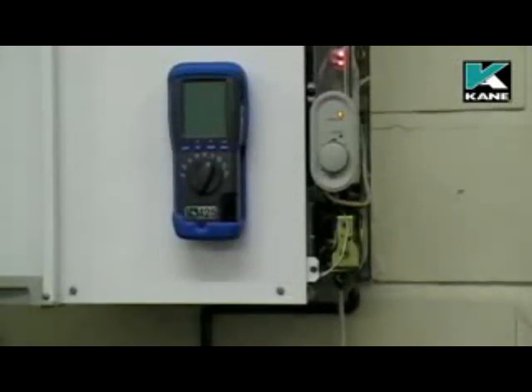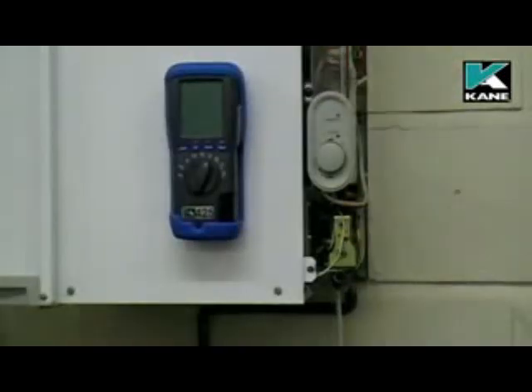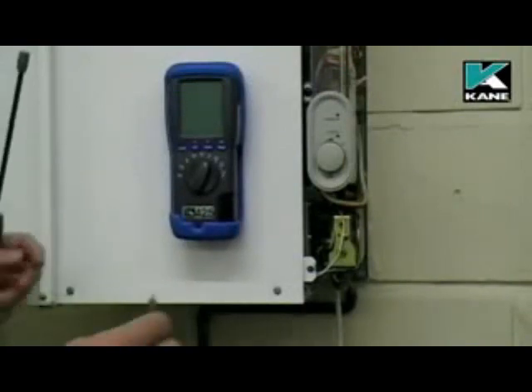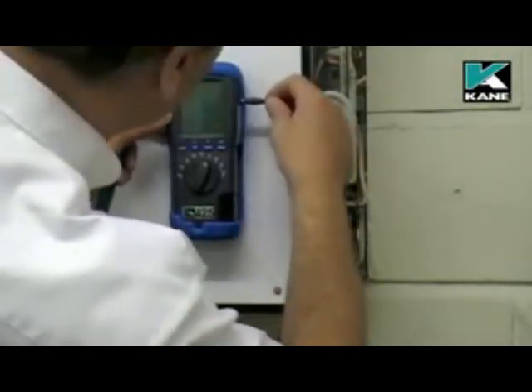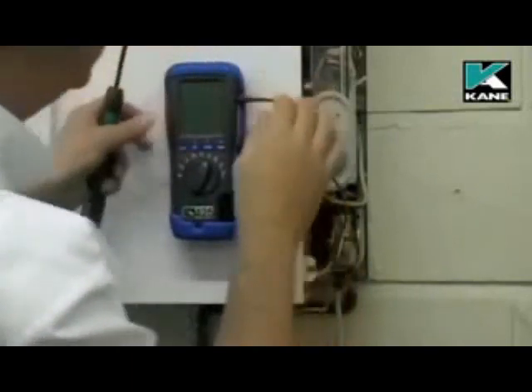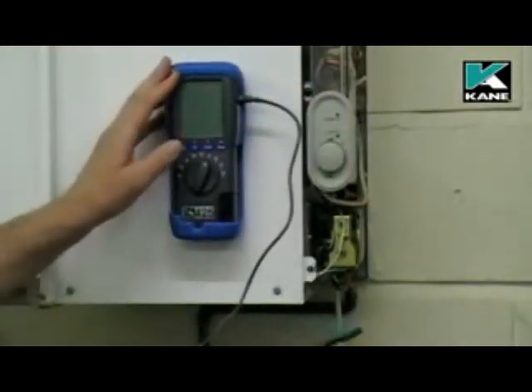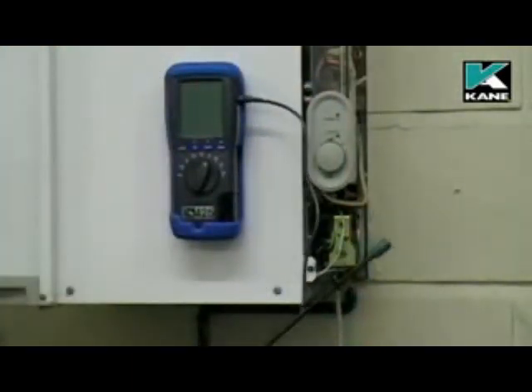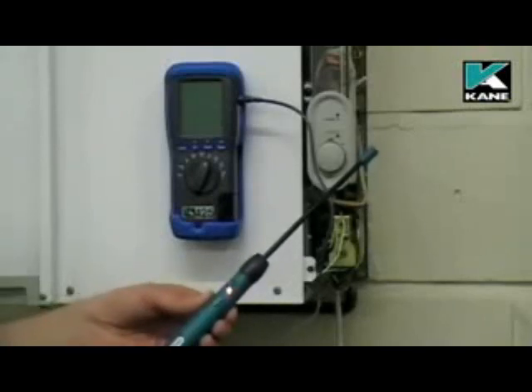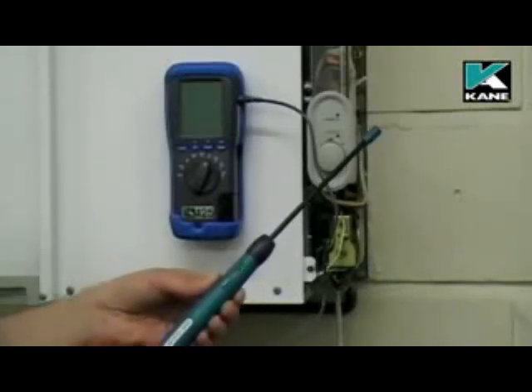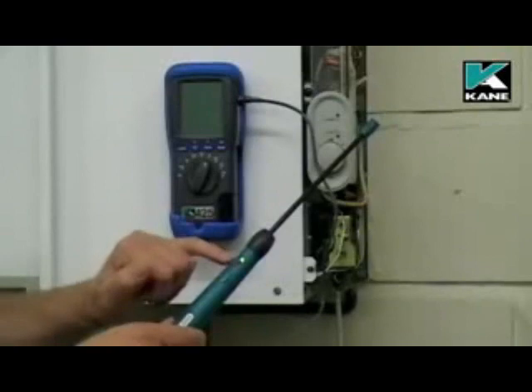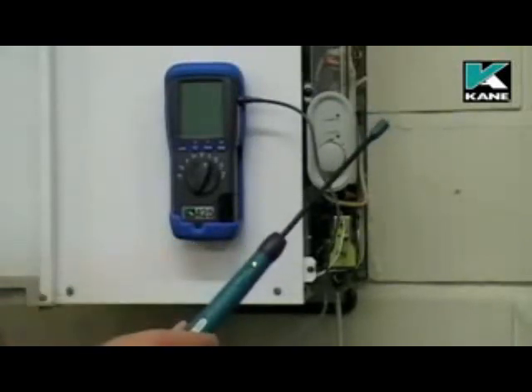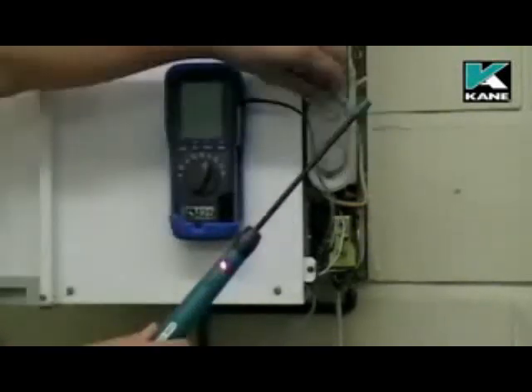Having set the burner pressure, I'm now going to use the optional gas leak detector to check that the test point is gas tight. To do this, plug the gas leak detector into the side of the analyzer. The analyzer just acts as a battery pack. Switch the gas leak detector on. It takes approximately 20 seconds to self-calibrate. So I'll just turn the boiler on now.